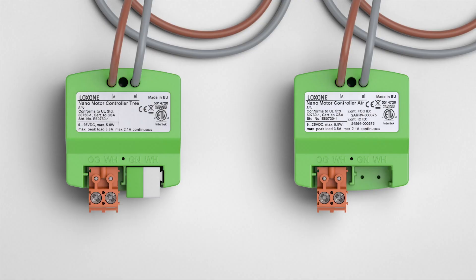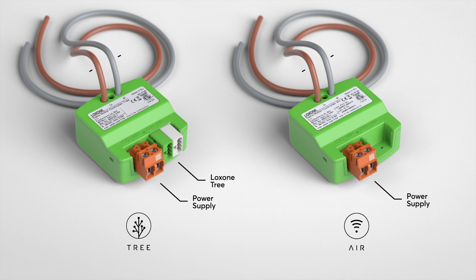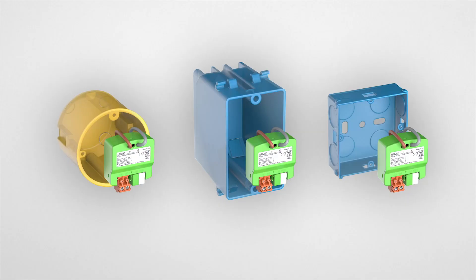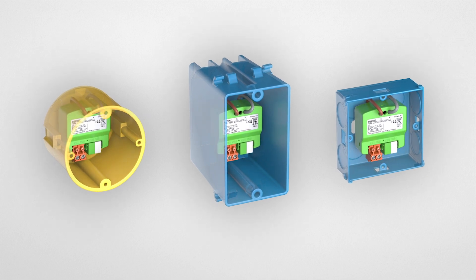The nano motor controller is available in Loxone Tree for wired and Loxone Air for wireless communication. Both versions are supplied with an operating voltage of 9 to 26 volts DC. The two outputs are pre-wired with 150mm long, 1.5mm² pairs of tails. Thanks to its compact design, the nano motor controller fits into standard circular, square, and rectangular back boxes.